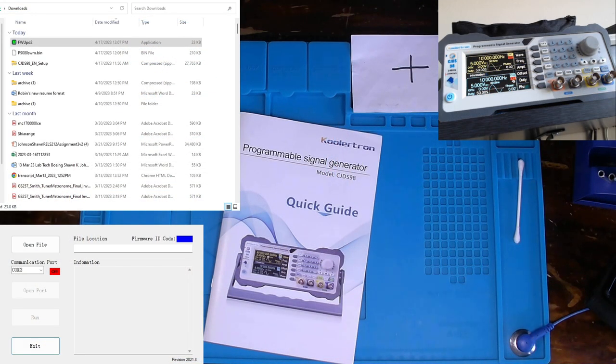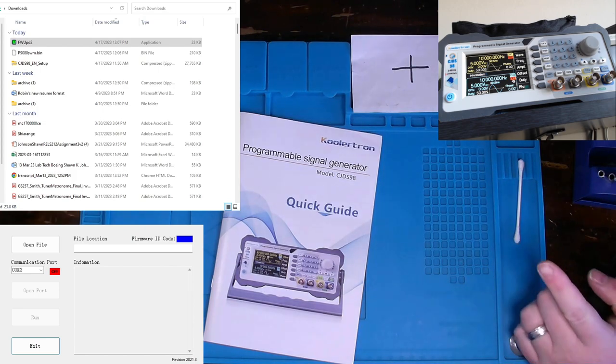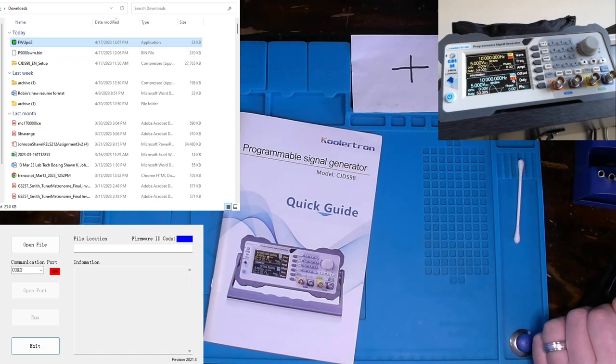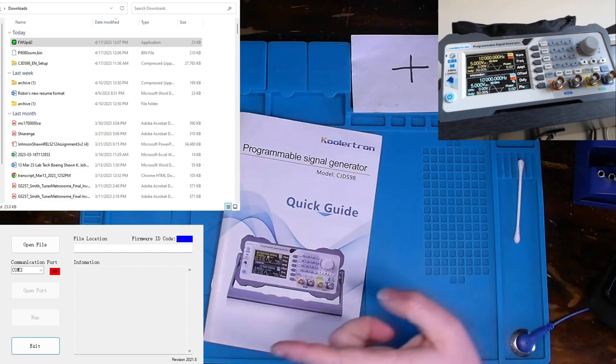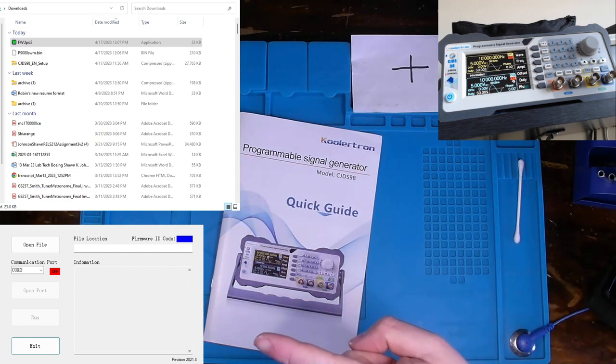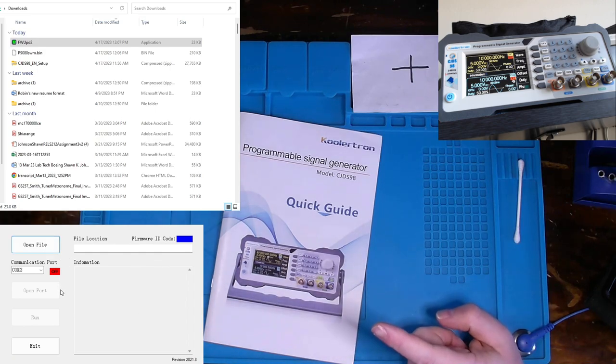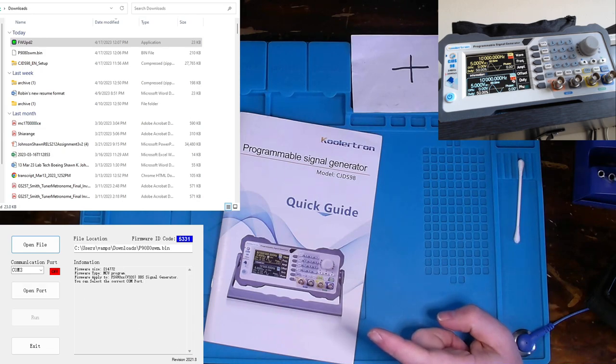All right. Okay, I just realized that a part of this I wasn't recording correctly, so apologies if this is a bit juddering. But from my download file, I am going to double click FW Update 2, which we downloaded from that website. Okay. And that will correspond to essentially what you see here on the bottom left hand corner. And then from there, I click open, and it'll pull up a new window where I can select the bin file, and I click open.